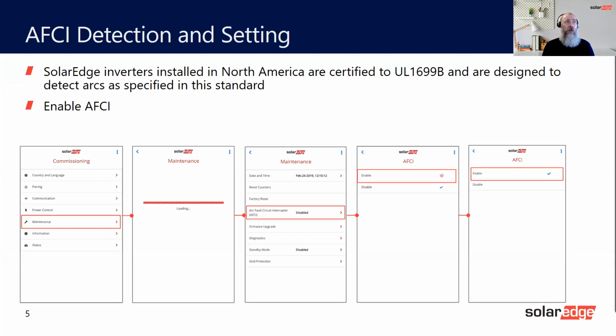Simply go to maintenance. After connecting with SetApp to the inverter, you then go to maintenance. You then go to arc fault circuit interruption. As you can see on here, it's disabled. Just here, this bit here, just disabled. And then you click on that, you click on the arrows here, and you switch to enable, and that's it done. Now we will be releasing a firmware. I think we're 2 firmwares away. Well, it automatically will set the arc fault circuit interruption to enabled.